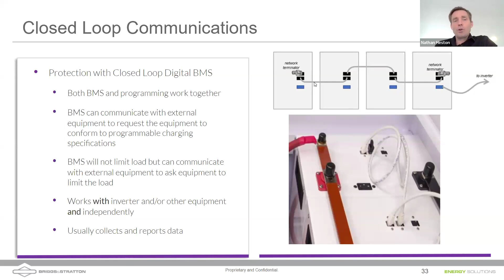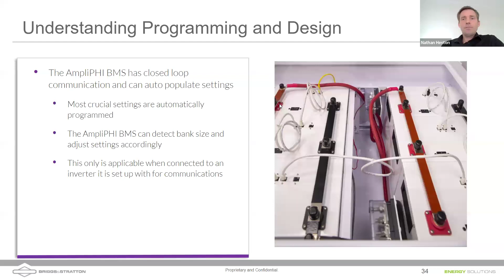Here it is all together, with two different battery sets bused together, bridging that gap: battery 1 to 2, 2 to 3, 3 across to 4, 4 to 5, 5 to 6, and then a home run from the last one out to the inverter. There's a terminating resistor on the left and another on the first one in the chain. Closed loop communications let the batteries tell the inverters, like a Sol-Ark inverter or a Briggs Stratton inverter, what the settings should be.